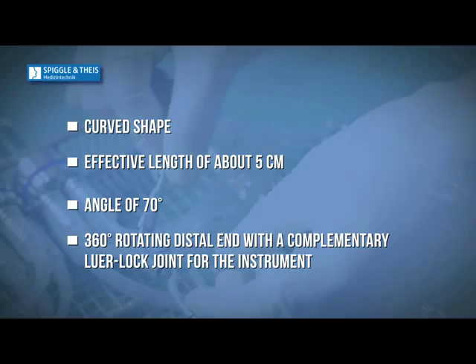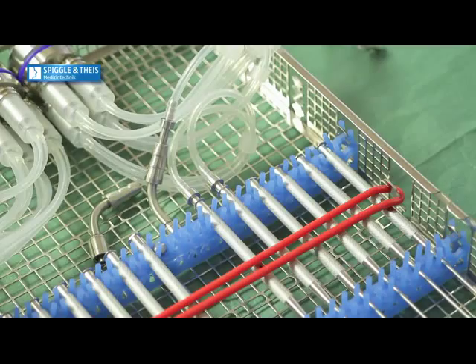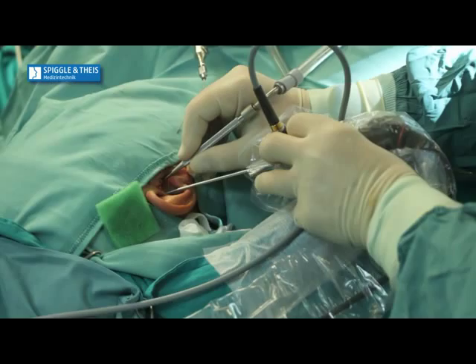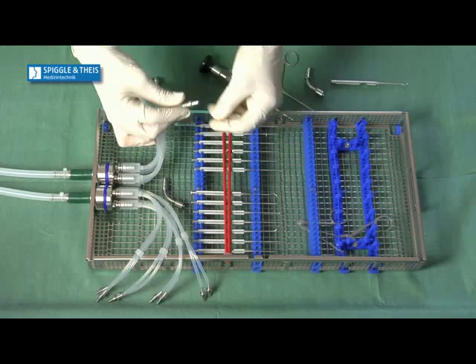The specific angle of the connector, together with the possibility of free rotation, ensures the reduction to a minimum of friction posed by the weight of the suction hose, which is engaged at the proximal end of the connector itself. This makes it particularly comfortable and facilitates the dissection.